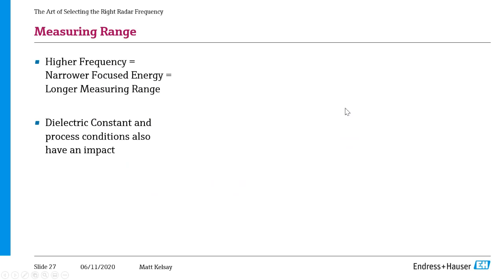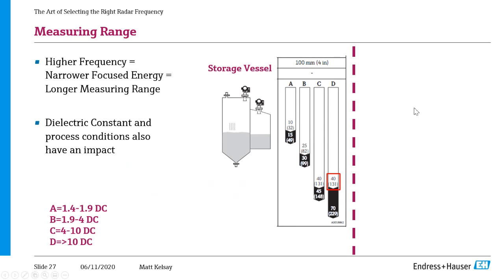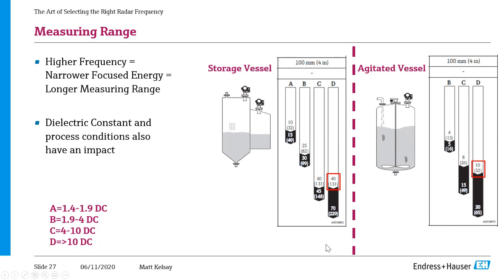Okay, next. So if we look at measuring range, this is along the same lines as the accuracy, but again, with higher frequencies, you're focusing that energy, which allows us to also measure further ranges. So higher frequencies, longer measuring ranges. In liquids, we can measure with high frequency up to something like 260 feet. I don't know of a tank that's that tall that holds liquids, but if there was one, we could probably measure it. In solids, it's even further than that. It's 400 plus feet. So I don't think there's a silo out there that is too tall for us to measure. However, it's also important to note that frequency is not the only thing that affects it. The dielectric constant, like we talked about earlier, and also process conditions have an impact on this. So go to the next.